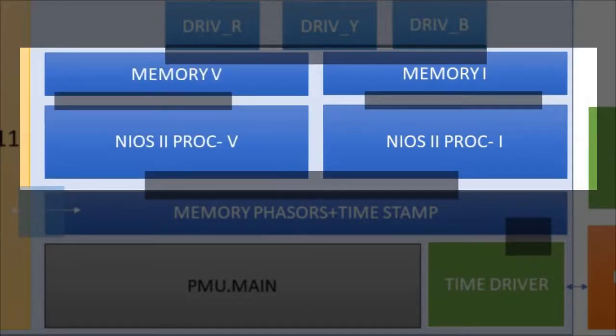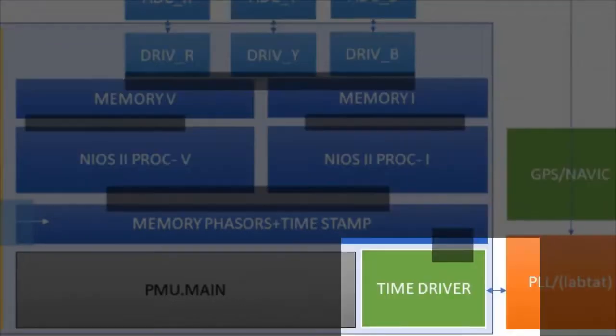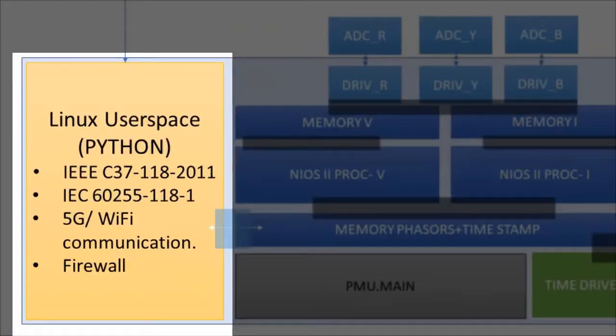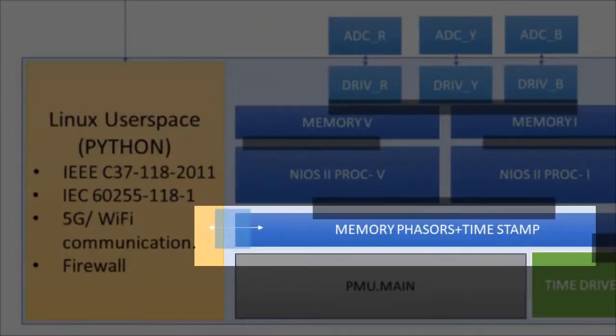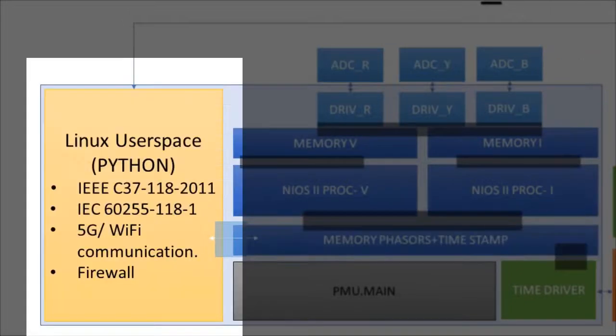After calculating the total six phasor values, three phasors for voltage and three phasors for current, the measurements are time tagged by invoking the time driver and finally stored in a shared memory. The ARM core collects those time-tagged phasor values from the shared memory and formats the measurements according to IEEE C37 standard and sends it to the PDC.